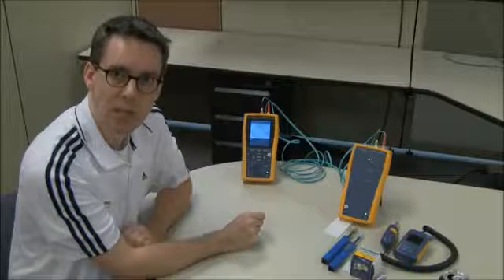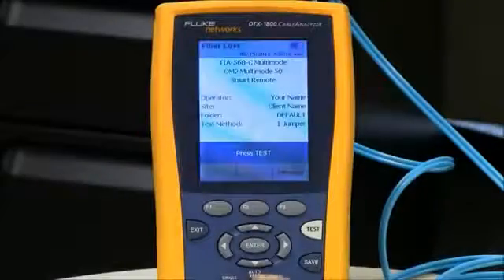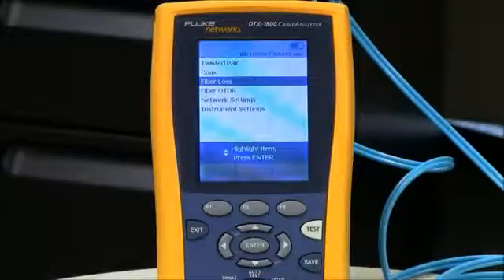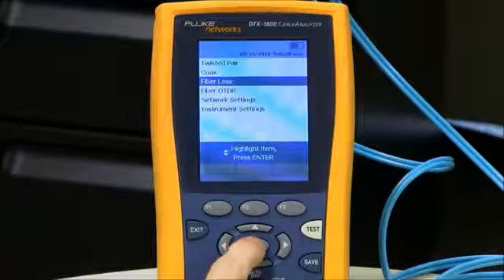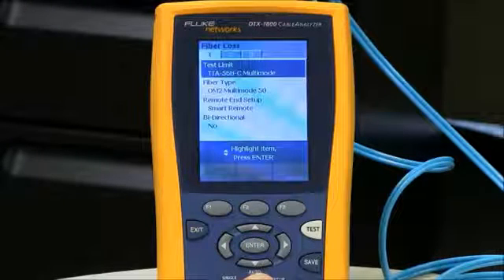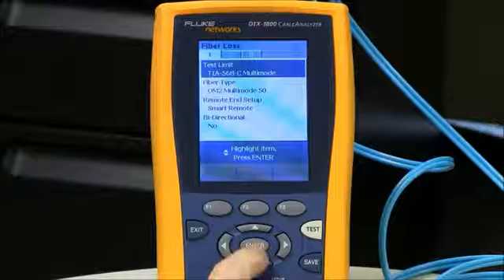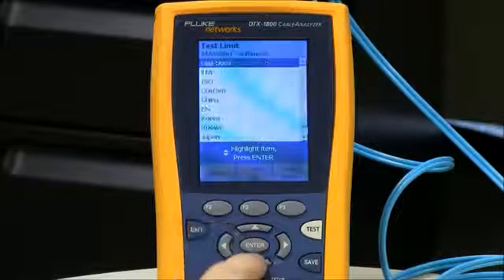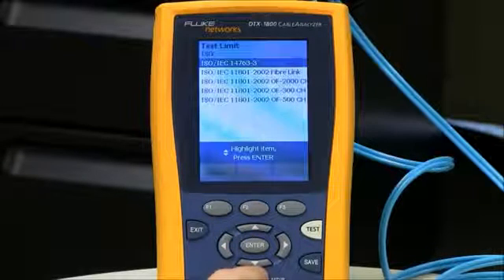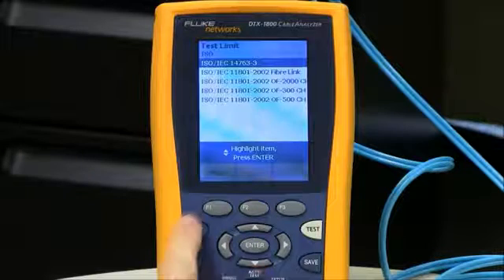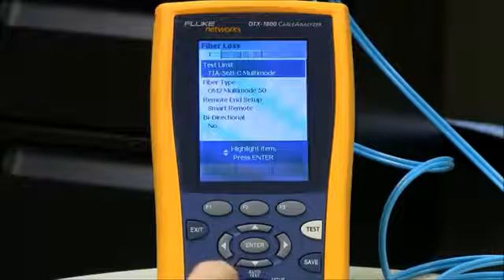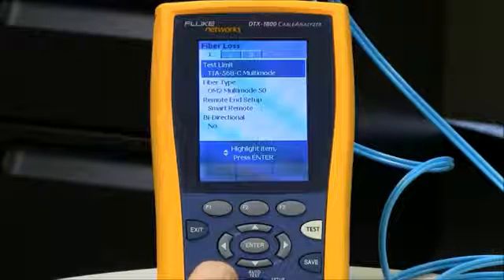Let's talk about setting up the DTX cable analyzer. I'm going to rotate the dial to setup, and with Fiber Loss highlighted, I'm going to hit the Enter key. My test limit is currently set to TIA. If I wanted to change that to ISO, I would hit the Enter key, F1 more, and go down to ISO, where I see the 14763-3 standard.